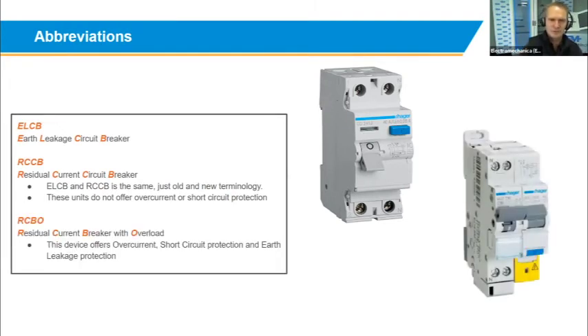Then you get an RCBO. An RCBO is a residual current breaker with overload. Unfortunately, I don't have a picture of a unit like this. It's not something that we at Electromechanical really sell into this industry because we've got other solutions, and it also becomes a fairly expensive solution. The RCBO looks like the normal RCCB, or earth leakage circuit breaker, but it has built-in short circuit and overcurrent protection. The disadvantage is that if something goes wrong on the circuit breaker part, you need to replace the whole unit. If something goes wrong on the earth leakage side, you also need to replace the whole unit. So that's why I think the norm, or the preferred way to do it in South Africa, is to use an earth leakage device like this and then just add a circuit breaker to it.